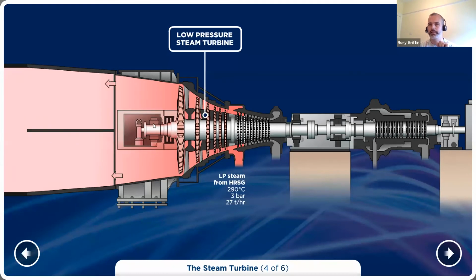Something to bear in mind here is this is the turning gear motor. So when Whitegate might get an instruction to come off from the grid, if it doesn't run for a few days, it sits on turning gear, which is typically about 4 RPM. And when it's on turning gear, this allows even cooling for the whole steam turbine rotor here. If you stop the shaft when it was red hot, you could get the shaft to thermally hog. It could actually bend a little bit.